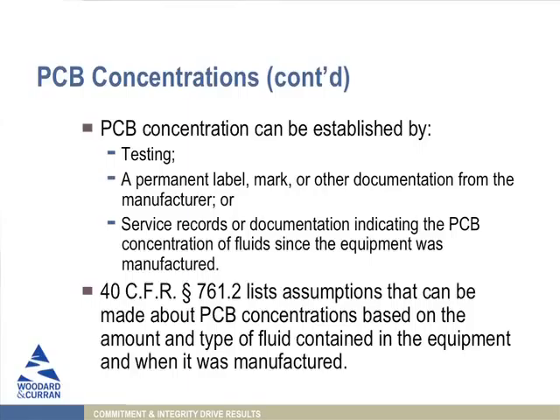If it is from closer to us, more recently than July 1979, you can presume it was less than 50 parts per million, because that was the key date after which it was no longer legal to manufacture anything in the United States with PCBs above 50 parts per million. So if you've got a transformer, capacitor, or light ballast with a manufacture date on it, that's the key date to look for.